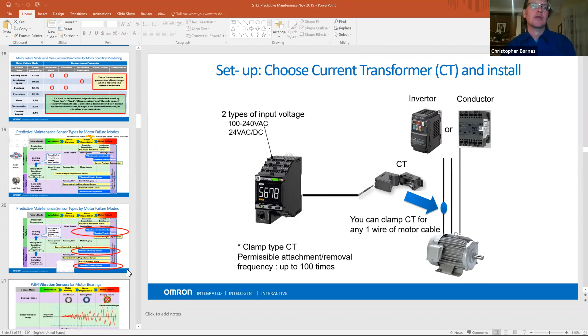Obviously, if you're changing the speed of the motor, you will see patterns that may show up in the vibration, but it shouldn't be abnormal. It should still be a smooth ride even at different speeds. You should be able to change the speed of the motor without it changing the vibration on the shaft - the motor will just be running faster or slower.